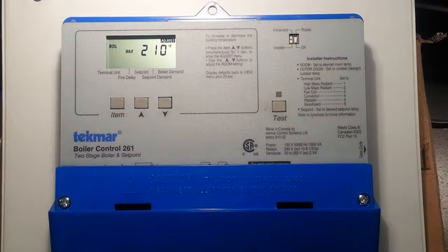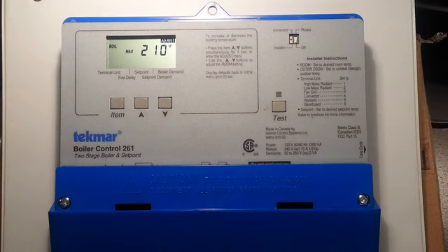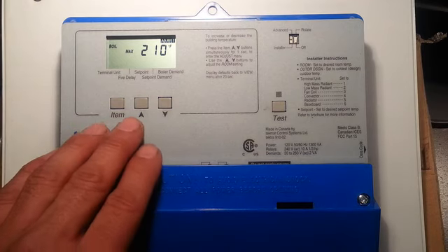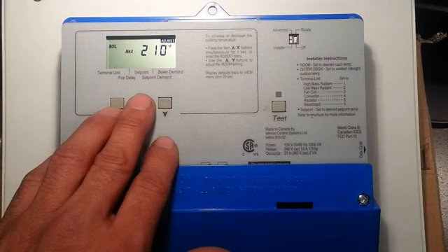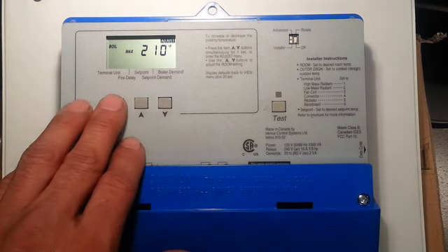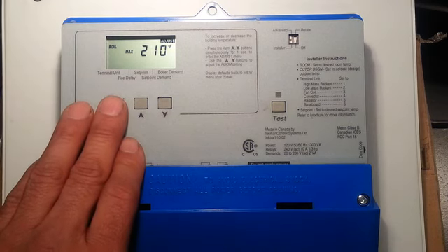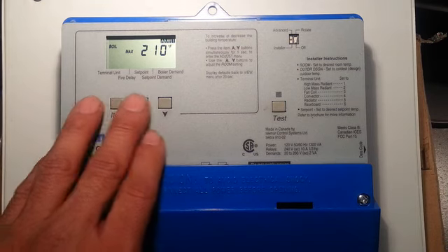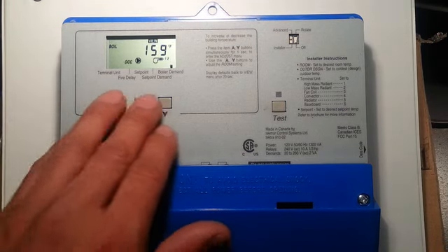The boiler maximum is typically set about 20 degrees higher than the boiler temperature in the previous setting, and that's because the extra 20 degrees gives the controller some differential to operate the boiler until the boiler water temperature reaches the 210, and then it shuts off and doesn't short cycle on the high limit.